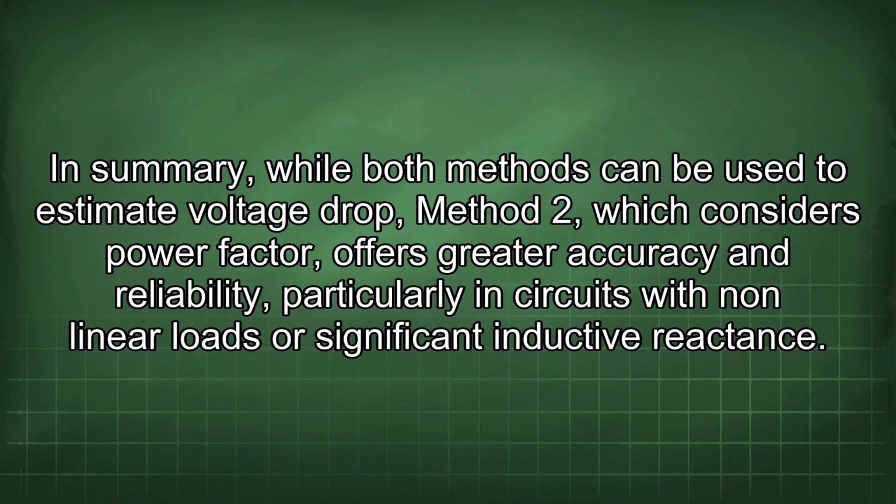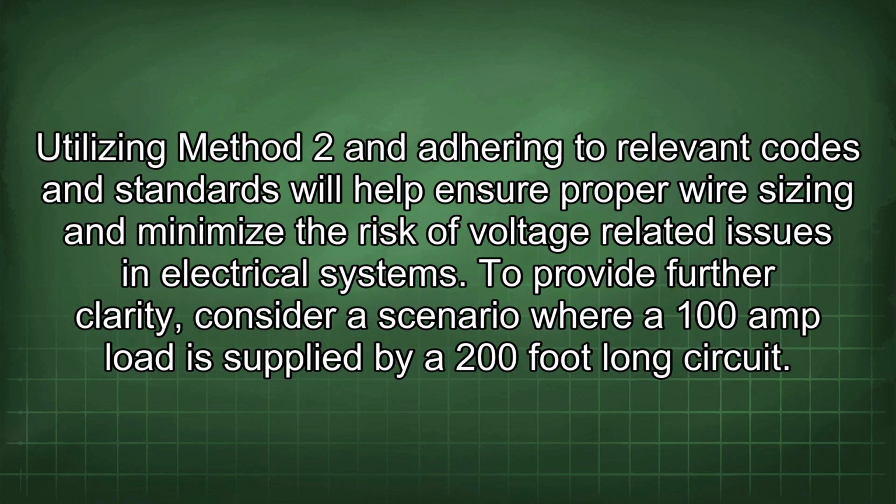In summary, while both methods can be used to estimate voltage drop, Method 2, which considers power factor, offers greater accuracy and reliability, particularly in circuits with nonlinear loads or significant inductive reactance. Utilizing Method 2 and adhering to relevant codes and standards will help ensure proper wire sizing and minimize the risk of voltage-related issues in electrical systems.